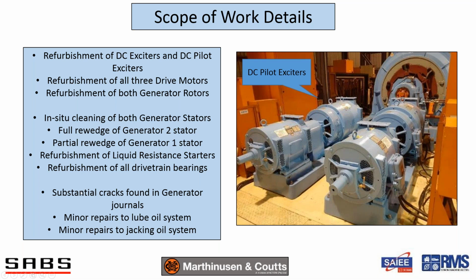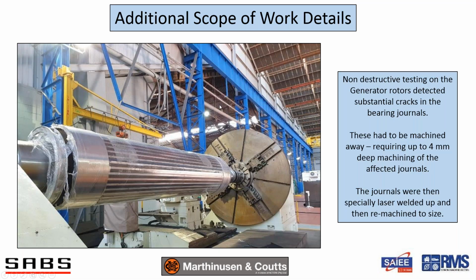And this is where issues occurred. We found substantial cracks in the generator journals. That's the main generators, and not just the small auxiliary units. It's the main generators, basically the heart of this plant. Minor repairs to the lube oil system and minor repairs to the jacking oil system. This is the one rotor in our lathe in our Benoni facility. And this is where you'll see there's absolutely no ventilation. Normally you'd see ventilation holes, or ventilation features in a 2-pole cylindrical rotor like this, and you see nothing, because they're not necessary, because the unit is only under load, and one hell of a load at that, but only under load for a very short period.